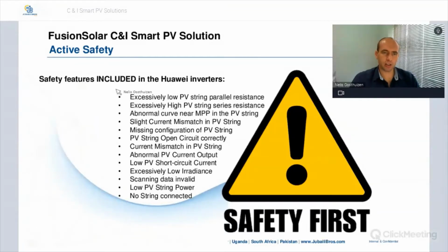I just want to add a note here: if you do pick up on your system that one of these faults or safety issues has been identified, do not ignore it simply because the inverter managed to restart a day or an hour or 3 hours afterwards without the actual fault being cleared. If a fault has been identified by the inverter, please do make time to actually inspect the fault to ensure that the installation is up to standard, because the inverter will not just flag these issues if they are not present. So this might affect your system in the long run. So please do have a look at the safety issues that have been highlighted by the inverter.